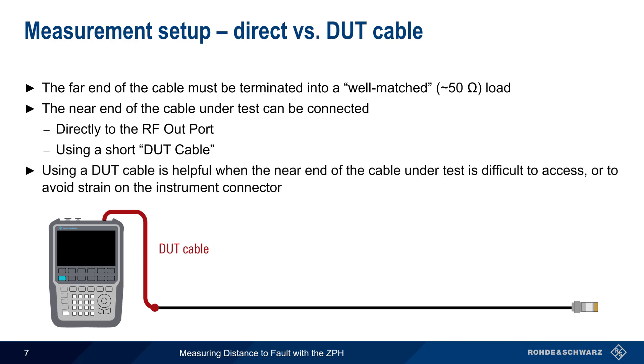A DUT cable may be helpful when the near end of the cable under test is difficult to access. Using a DUT cable also helps to avoid strain on, or damage to, the analyzer connector. As we'll see in a few minutes, the effect of this DUT cable can be removed as part of the calibration process.